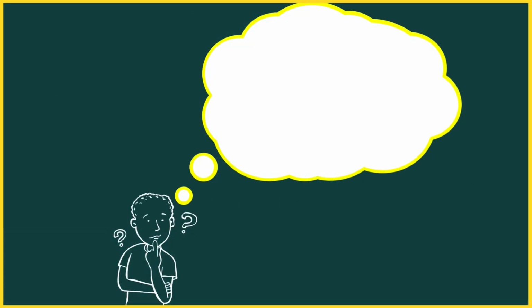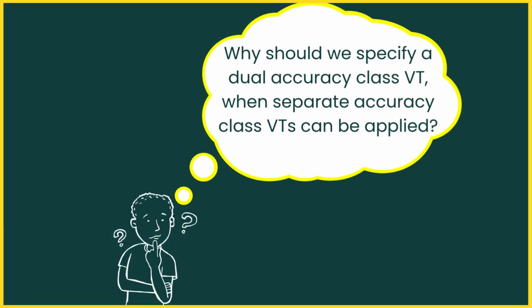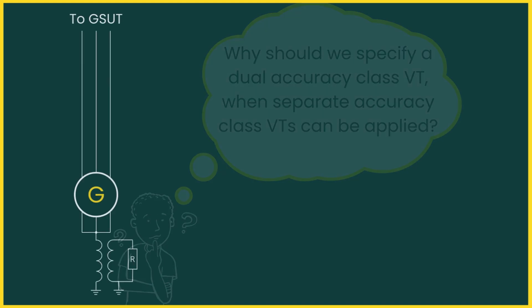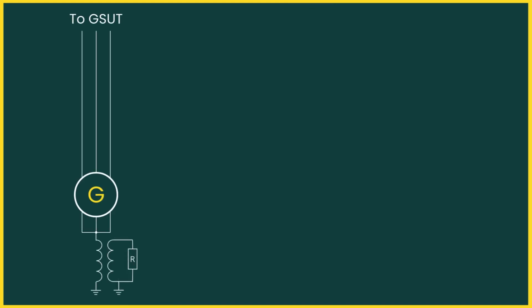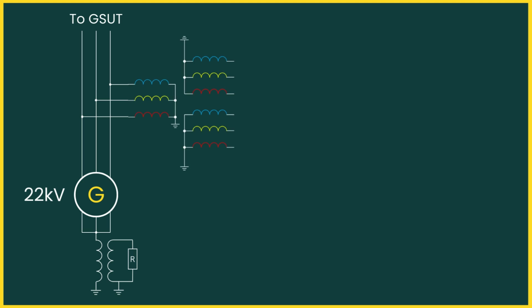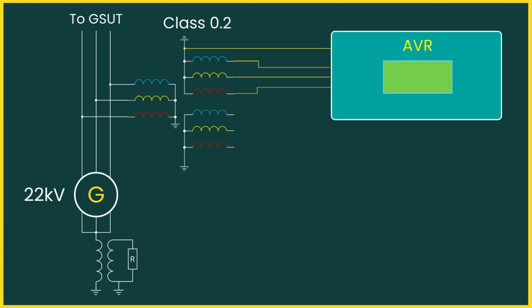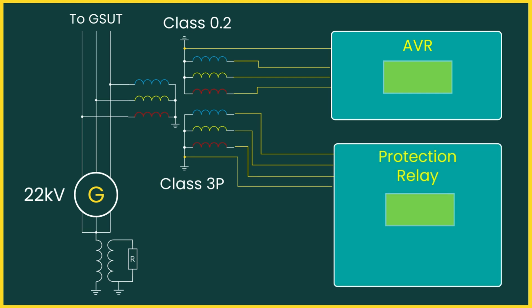At this point, you might be thinking, why should we specify a dual accuracy class VT, when separate accuracy class VTs can be applied? Let me show you how this exact misconception has caused nuisance tripping in a power plant. A generator at 22 kV had a VT with two secondary windings. One winding was designed for class 0.2 feeding the AVR. The other winding was designed for class 3P feeding the protection relay.